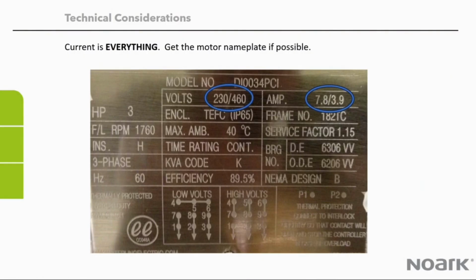When selecting a drive for an application, ideally, getting the motor nameplate would be the best case scenario, allowing you to properly size it. But in the absence of that, voltage, amperage, and application would be the key points of information that should be obtained to be able to properly select the appropriate drive.